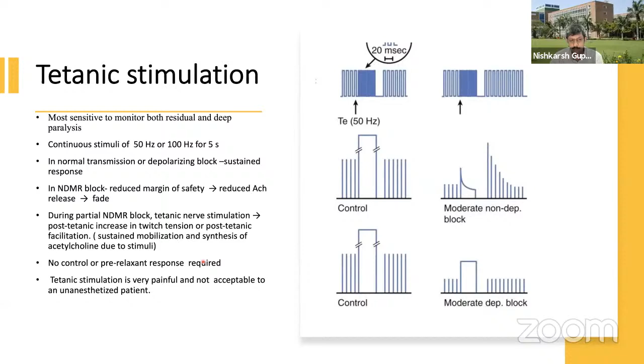Then coming to the post-tetanic count, this is another important monitoring technique. A tetanic stimulus of 50 Hertz is applied, and this is followed 3 or more seconds later by multiple single twitches. So we give a tetanic stimulation of 50 Hertz, and then we give multiple single twitch stimuli, 1 second apart, 3 seconds later. As the intense block dissipates, we start seeing a post-tetanic count due to facilitation, because of accumulation of acetylcholine, as we discussed earlier. The number of post-tetanic twitch responses we see is directly proportional to the return of the first response of TOF. So basically, if we see a post-tetanic count of 10, the TOF ratio of 1 is around the corner. It generally comes within a few seconds to a minute.